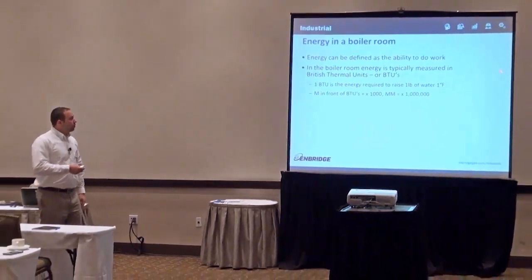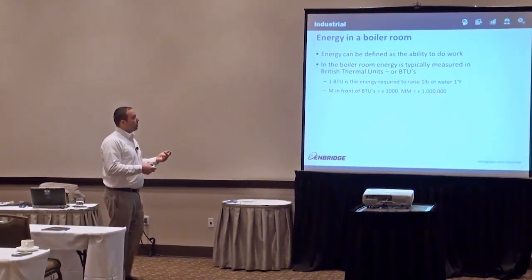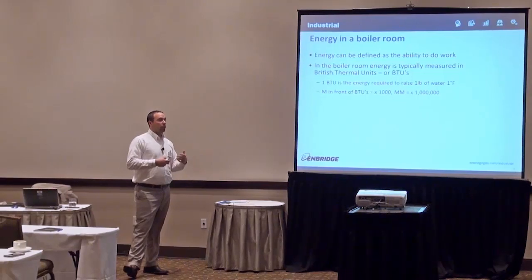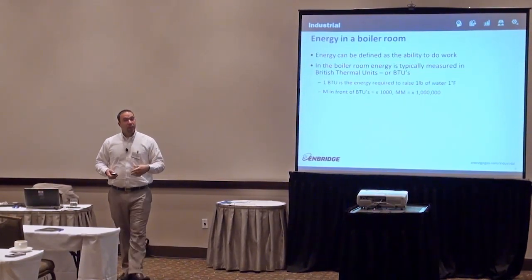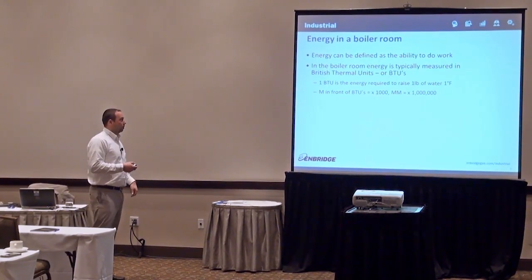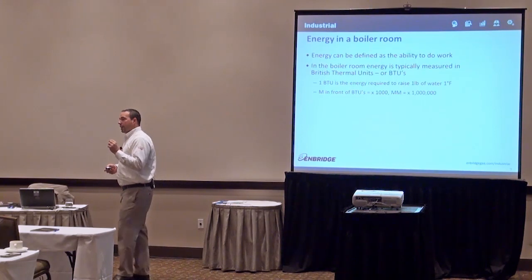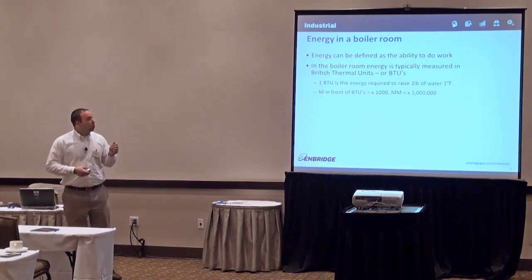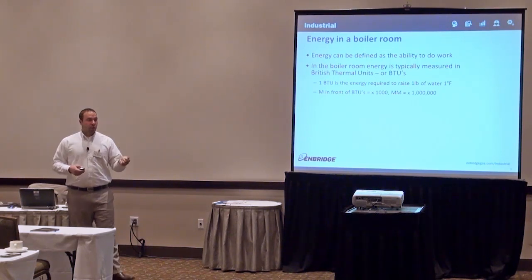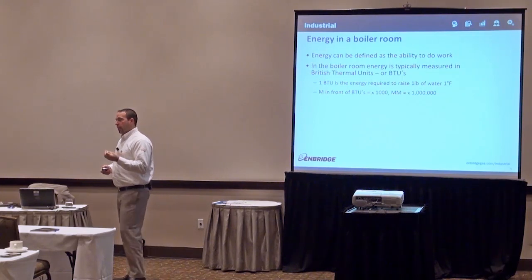One very confusing part with BTUs is that if you put an M in front of it, it means 1,000, and if you put in two Ms in front of it, it's actually 1 million. So if you hear somebody saying 5 MMBTU, that's 5 million BTUs per hour, which is a little bit different than how we do it in the metric system. A BTU can be defined as the energy required to heat 1 pound of water 1 degree Fahrenheit. So it's actually a very tangible energy unit.